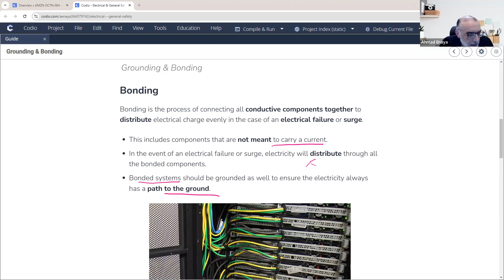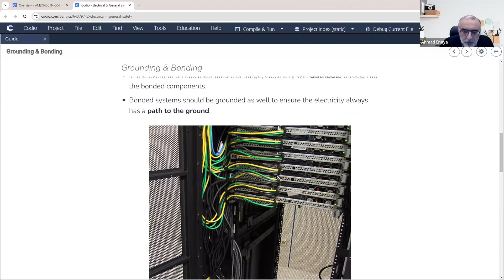So this is an example of how different devices, these are servers, are connected to a common bond or common ground. And typically in any installation guide, you will find instructions on how to connect this bond connector. In the back of any switch or router or server, you'll find a place for a screw, and they also include a short cable. Typically it will be a yellow cable with a nut where you screw it to the back, and then on the other side you screw it to the rack, and this way you make sure all these devices are bonded together. I may have some photos.